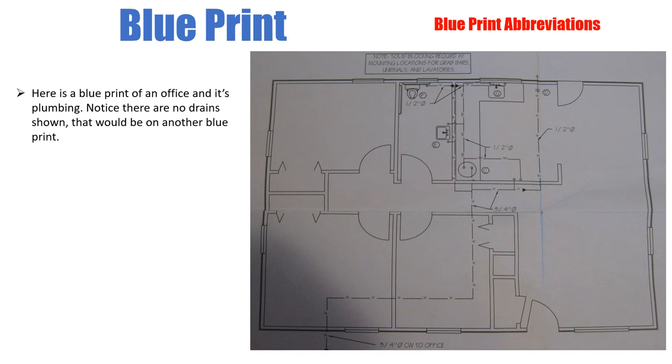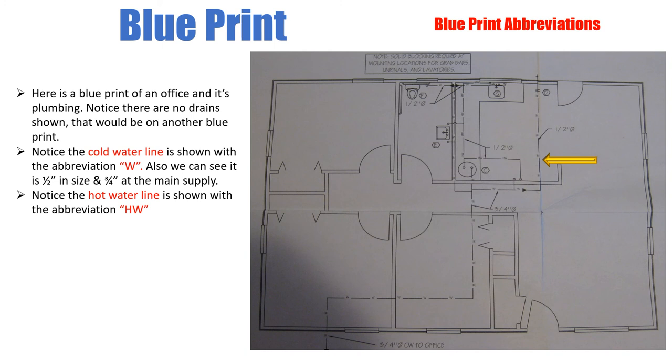Okay, so here's a blueprint of an office and it's plumbing. Notice there's no drain line shown, so that would be on a separate blueprint. Notice here the cold water line is shown with the abbreviation W. Also we can see it is half an inch in size and three quarters at the main supply. So here's our main supply coming in, it's labeled three quarter inch. Cold water to the office comes in through here, stops there. So this is all three quarter inch plumbing, and the half inch lines are shown here. And we have a half inch line here also.